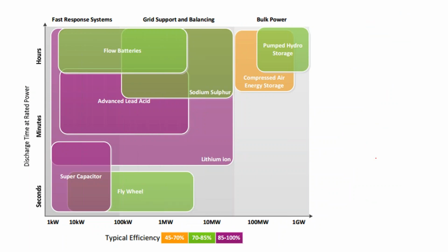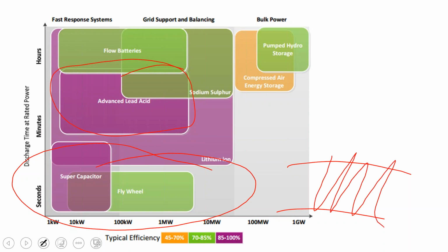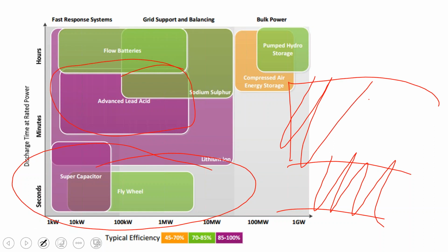Likewise, if we had one issue, there's other ways to manage your energy, which we'll get into. Flywheels and supercapacitors, their niche is more when you're charging and discharging in a matter of seconds. Now, with commercial demand management, it's being itemized by a 15-minute period or a 30-minute period. So you don't need a response time of seconds, you just need a response time of minutes.